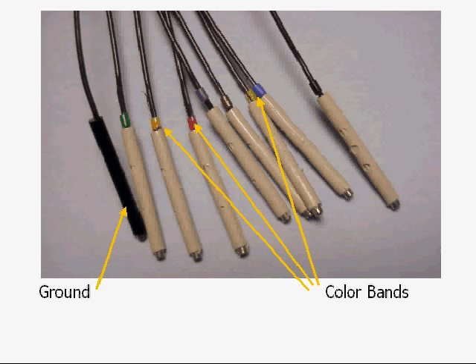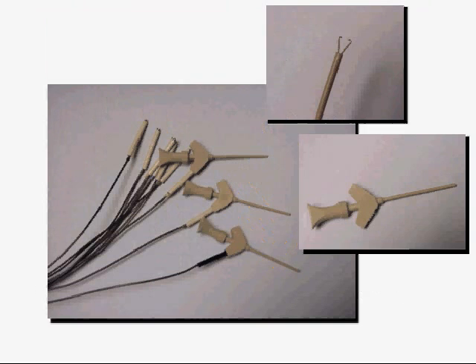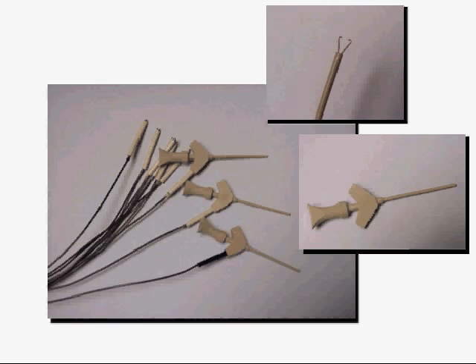A closer look at the end of the acquisition cables shows the ground line clearly designated in black, along with the other color bands used to simplify correlating signals in the software. Finally, we have the connectors that plug into the end of the acquisition cables. One of these must be placed on the end of each signal line that you will be using. They preserve the integrity of the acquisition cables and data collection should not be performed without them.